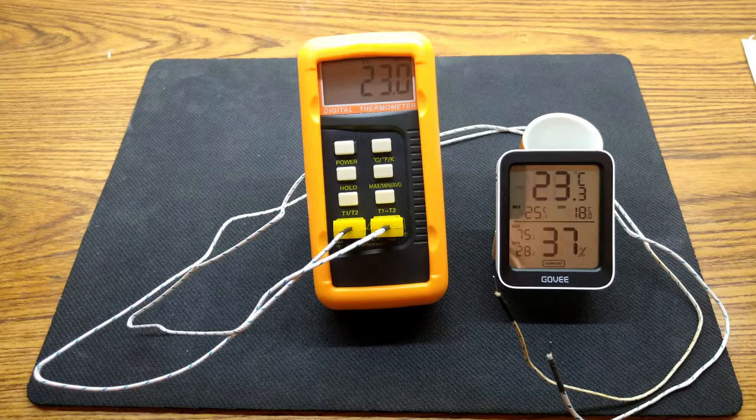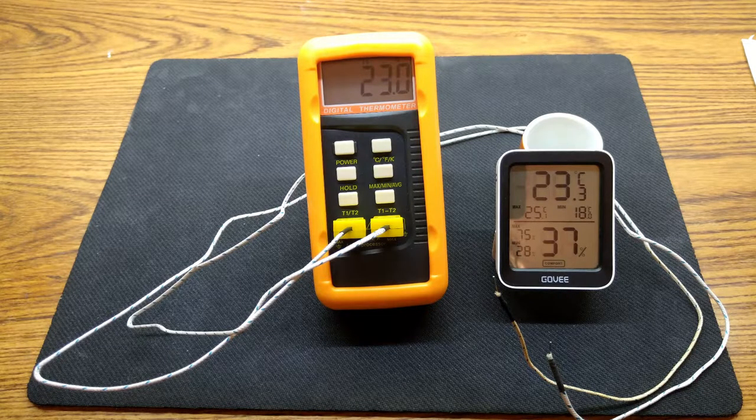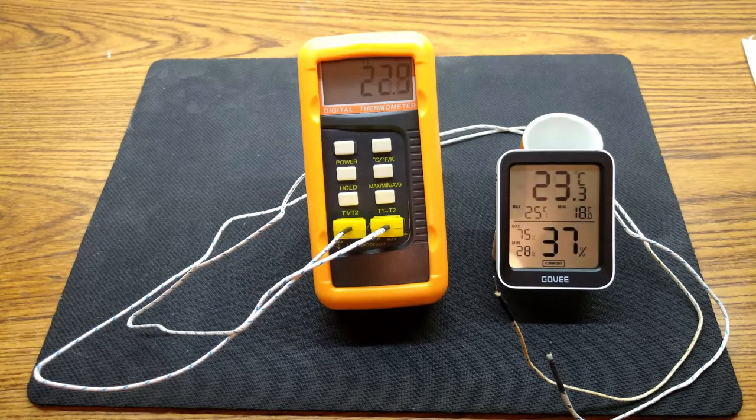However, since most people buying something this cheap won't want to or even be able to perform a multipoint calibration to confirm this, I'm going to go ahead and test it at 0 and 100 degrees Celsius to see how close it is.